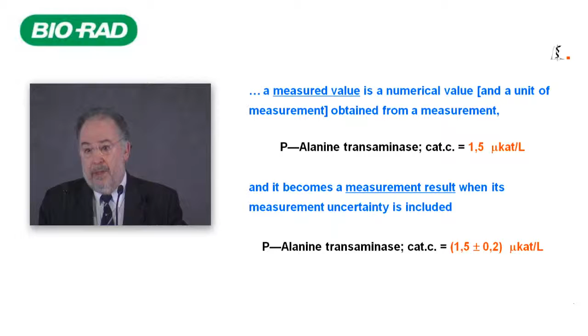In clinical laboratory science, a measurement is made to obtain a measured value that can reasonably be attributed to a quantity. And a measured value is a numerical value and a unit of measurement obtained from a measurement. This is the typical expression of a clinical laboratory result from IUPAC. In the first example, 1.5 microcatals per liter is a measured value, not a result. To become a result, it is necessary to add the uncertainty of measurement. In the second example, in the parentheses, this is a real result because there is the measured value 1.5 and the uncertainty. In this case, it is an expanded uncertainty.